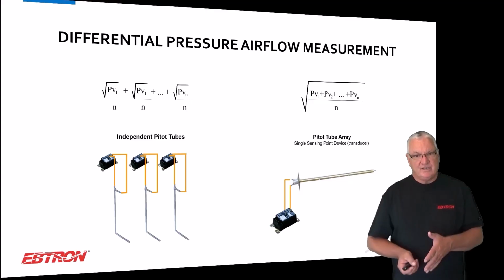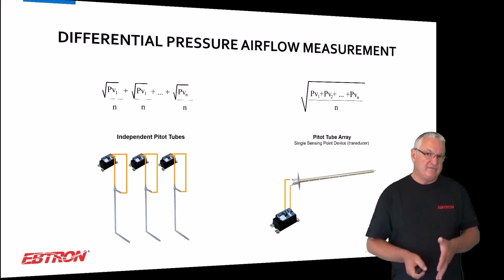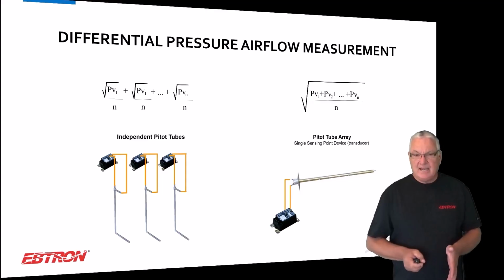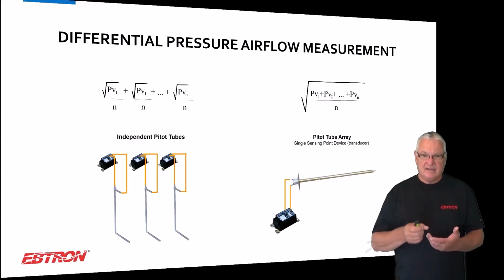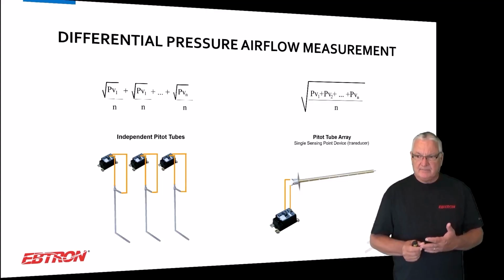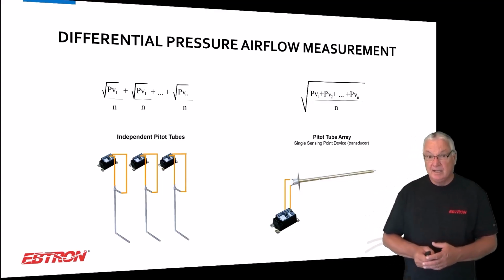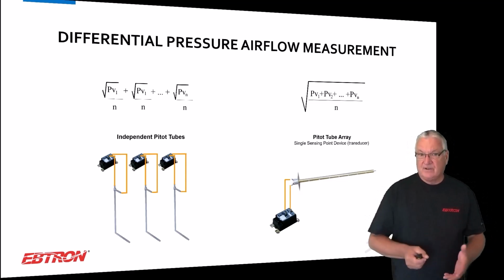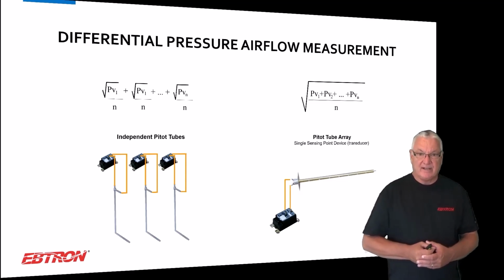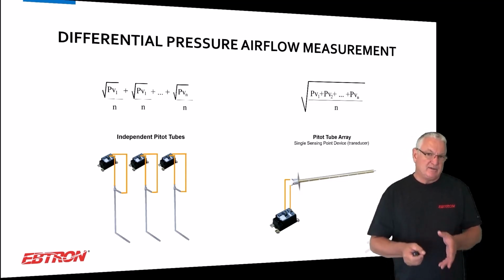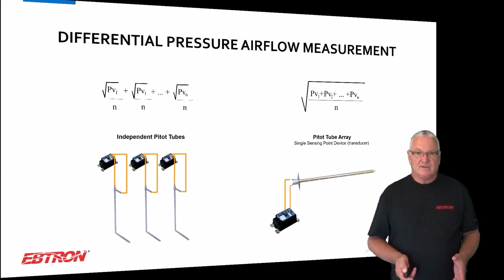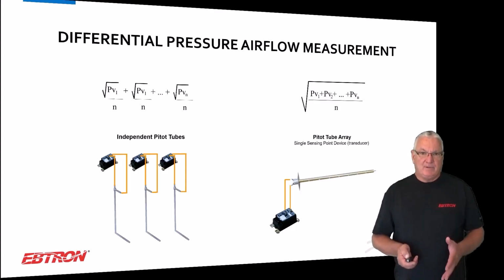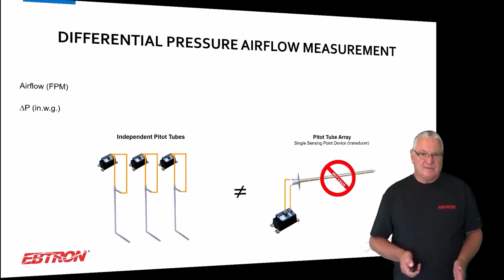But what an averaging device will do, the best it can do, is give you the average velocity pressure. Doesn't matter what it is. Like I said, it could be a pitot array, it could be an air wing, it could be a fan inlet piezo ring. It's even worse on a series of piezo rings on a fan array. I'm just going to show it on this one way. I don't want to spend all day on this, okay? But anyhow, apply some numbers to it.